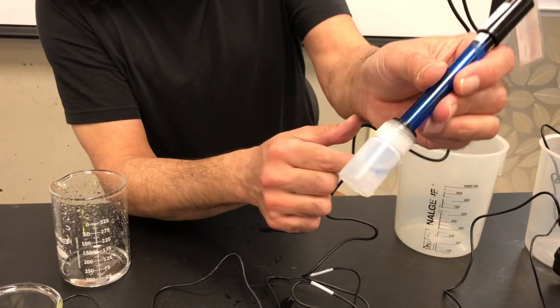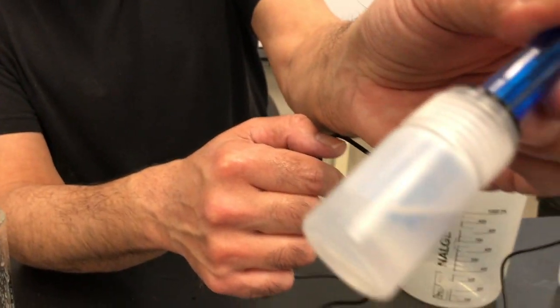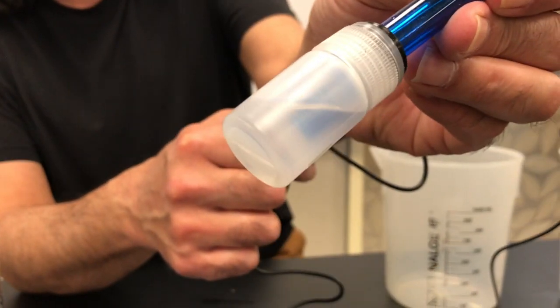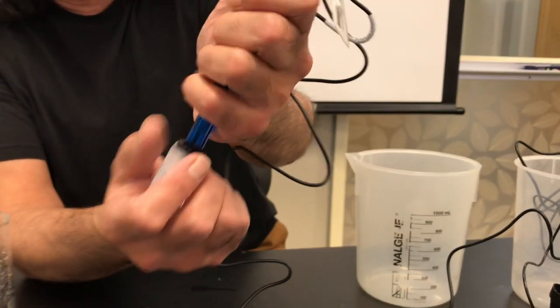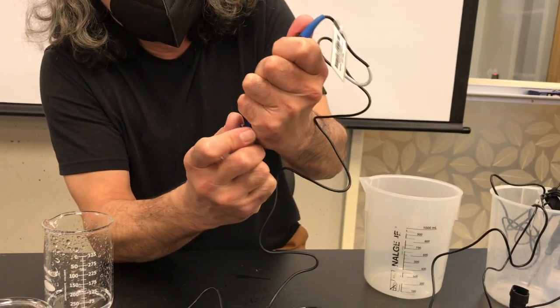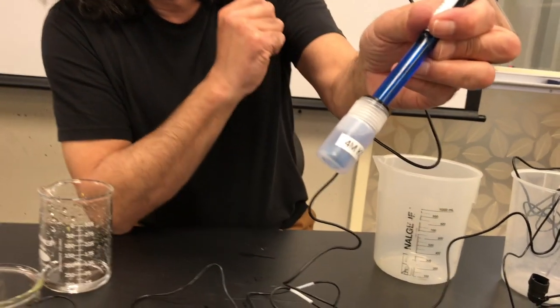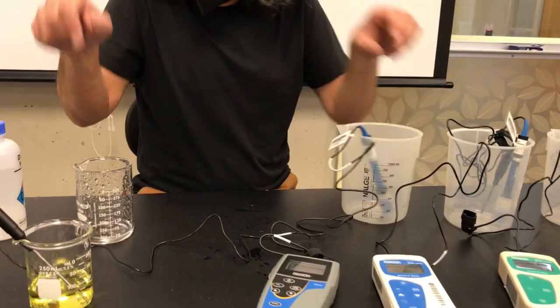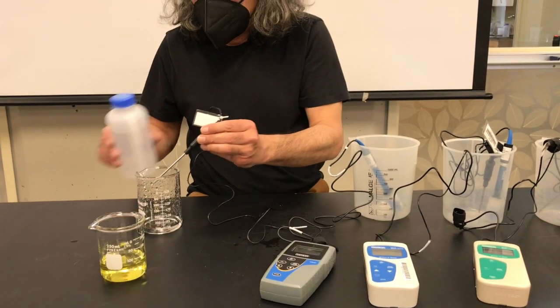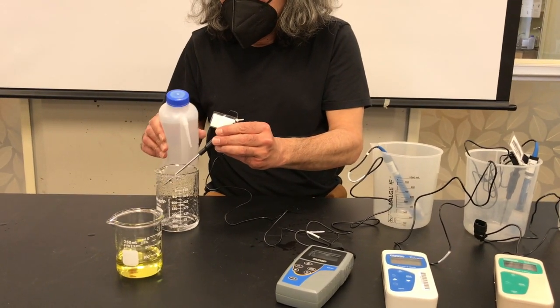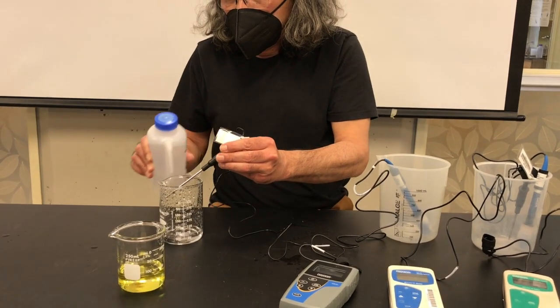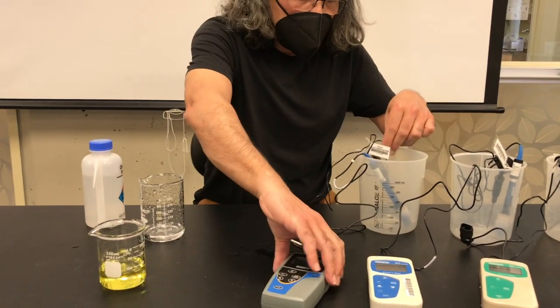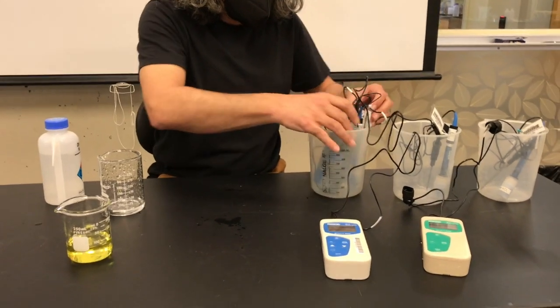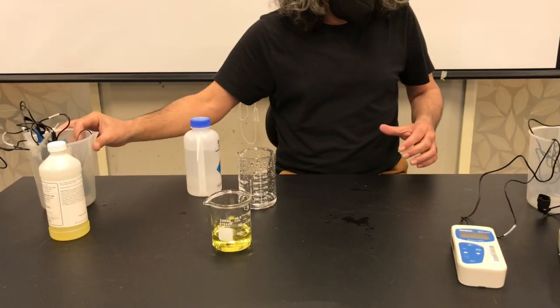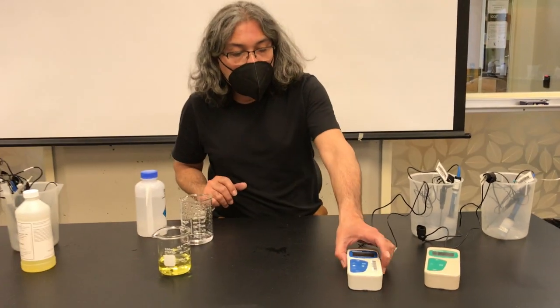Then look, I'm going to have to push the meter farther down on the bottle to make sure the membrane is submerged, because right now it's barely submerged. So I'm going to carefully adjust that and push it all the way till it's submerged like this. This goes back here, and don't forget to rinse the temperature probe as well. Just DI water, shake, shake, shake, and it can go back on its bucket.